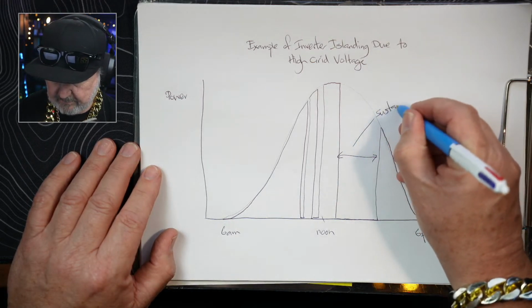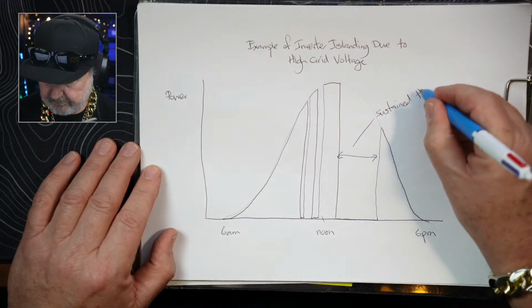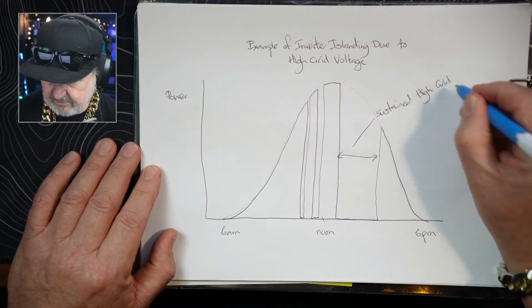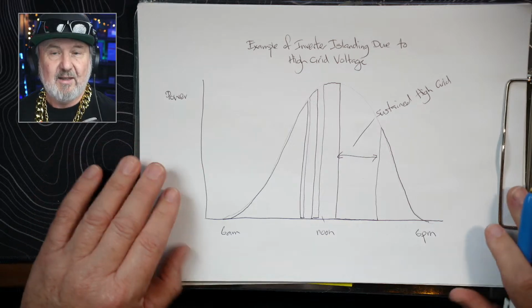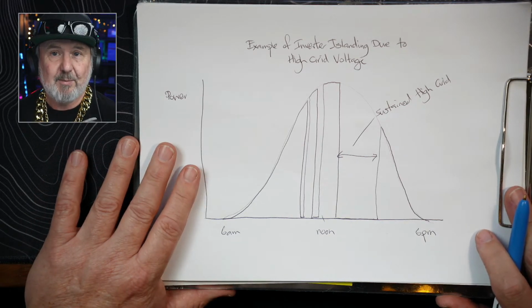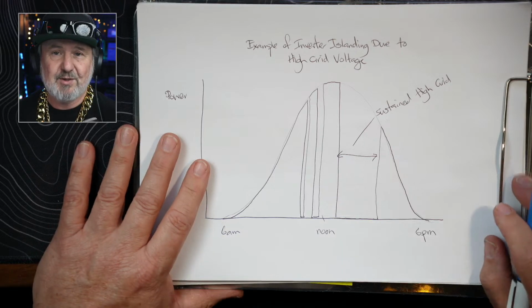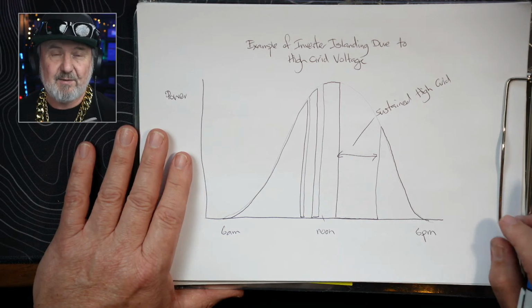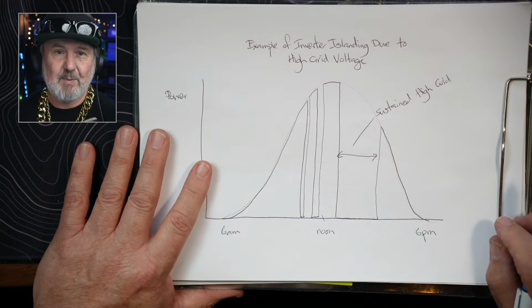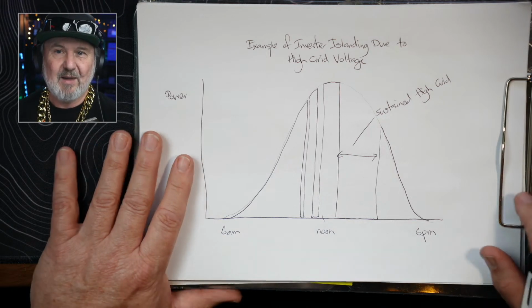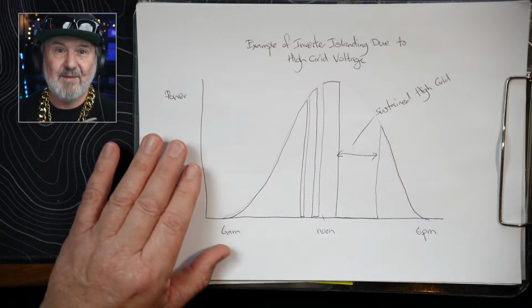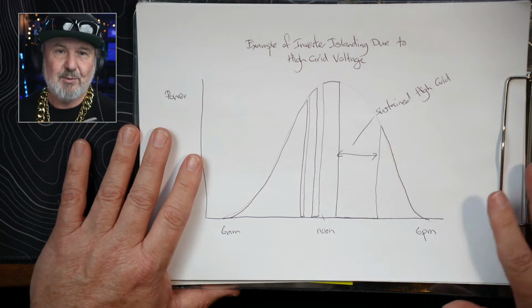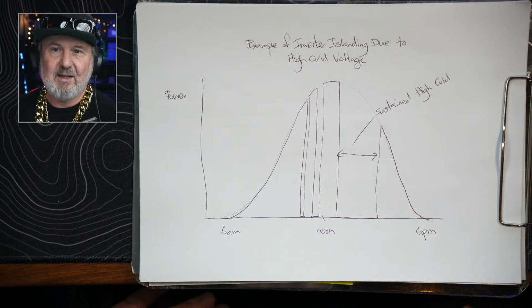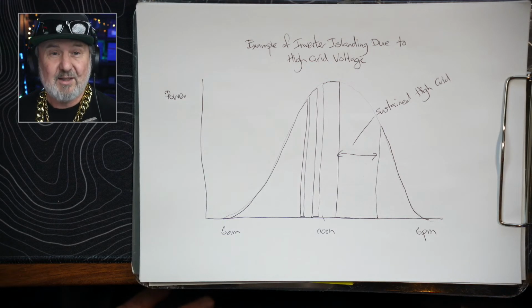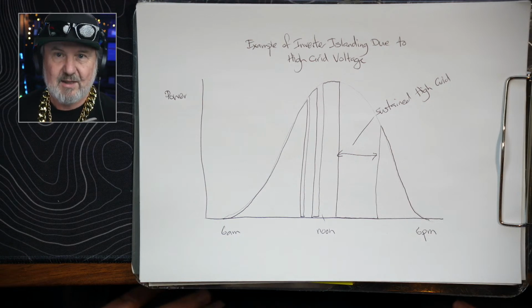And that's because there's a whole lot of other generators on your phase pumping away as well. This can also filter across the network, because electricity flows in both directions through a transformer, so it goes back up the high voltage. Transformers are basically dumb - they just have a ratio between their input and output, and that ratio means that as the voltage goes up on the low voltage side, it'll also go up on the high voltage side. So that's what it looks like.